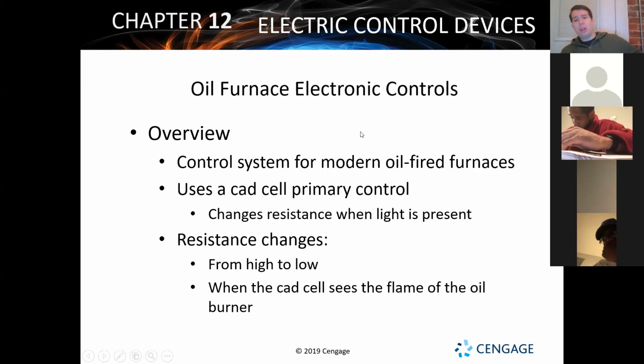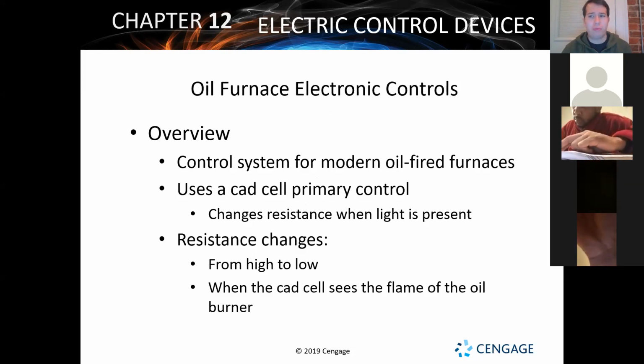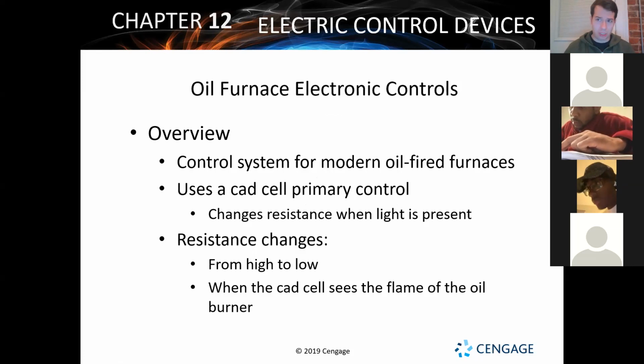Oil furnace. The big thing with an oil furnace is, first of all, this is the dinosaur. All right, this is how Grandma and Grandpa had been heating their house for a long time. If not this, they probably used coal. They might have had natural gas or propane, but oil, man, been around for a minute. You got a whole class where we just cover oil furnaces, but the big thing to get with it is it's got a weird, unique safety called a CAD cell.